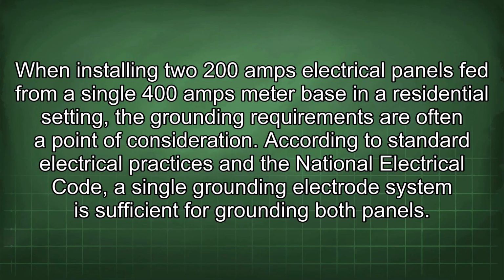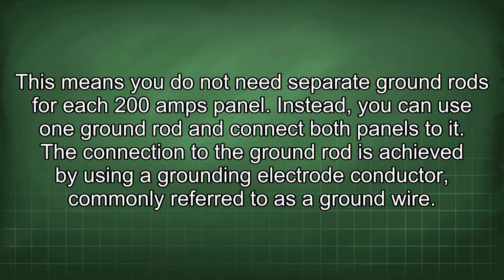When installing two 200 amp electrical panels fed from a single 400 amp meter base in a residential setting, the grounding requirements are often a point of consideration. According to standard electrical practices and the National Electrical Code, a single grounding electrode system is sufficient for grounding both panels. This means you do not need separate ground rods for each 200 amp panel. Instead, you can use one ground rod and connect both panels to it.